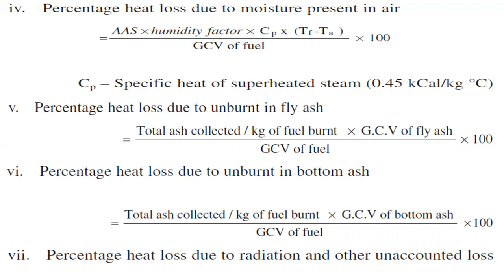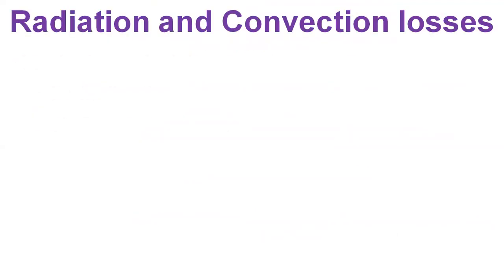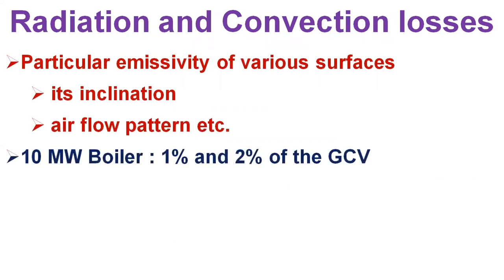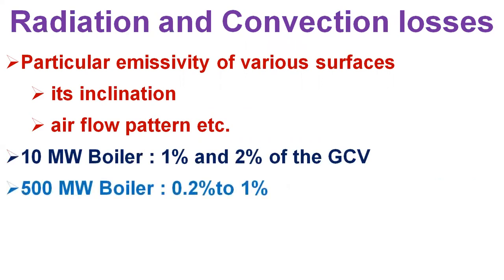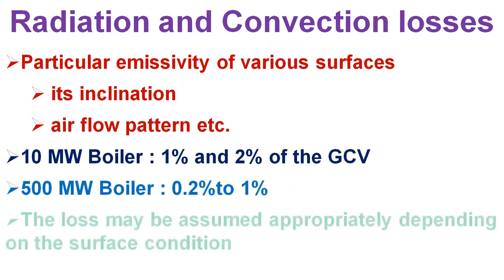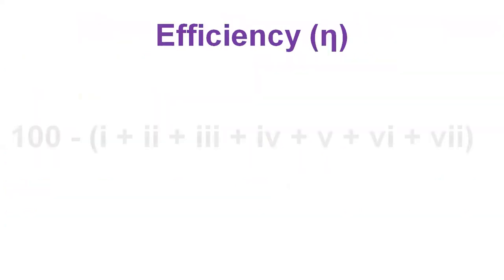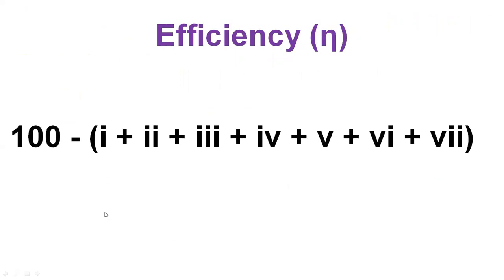Finally, the percentage heat loss due to radiation and other unaccounted losses: actual radiation and convection losses are difficult to assess due to emissivity of various surfaces, inclination, airflow pattern, etc. For a smaller boiler with capacity of 10 MW, radiation and unaccounted losses could amount to 1–2% of the GCV of fuel, while in a 500 MW boiler, values of 0.2–1% are typical. The boiler efficiency is then equal to 100 minus the sum of all these loss percentages.